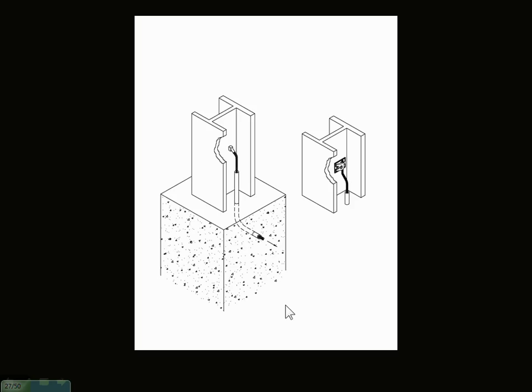The other thing you can do is, if your house is sitting on really poor soil quality, run what's called a counterpoise system. That interconnects every single ground rod at grade and gives you a better resistance rating. A lot of houses in Florida do it because they're sitting on beach sand, which isn't good soil quality for a lightning protection system. So we connect all the ground rods to make it a little bit better of what we call an ohm rating, or ohm resistance.